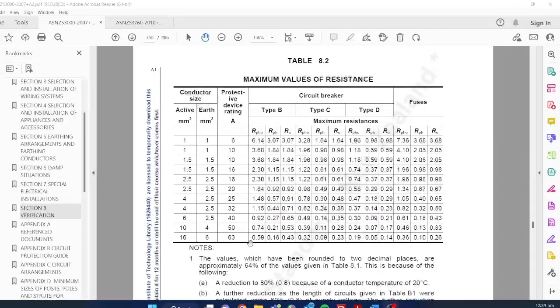Table 8.1, table 8.2, maximum values of resistance. Now, this is dependent upon the conductor size and also the protective device that is connected there. When I say protective device, I mean typically an MCB, a circuit breaker. The reason for that is because the purpose of the earth conductor is to carry a fault current if there is a fault, and depending on the rating of this device, the fault current of the MCB protecting my circuit can be more or less. So a 10 amp circuit breaker will trip with less fault current than a 20 amp circuit breaker, for example.